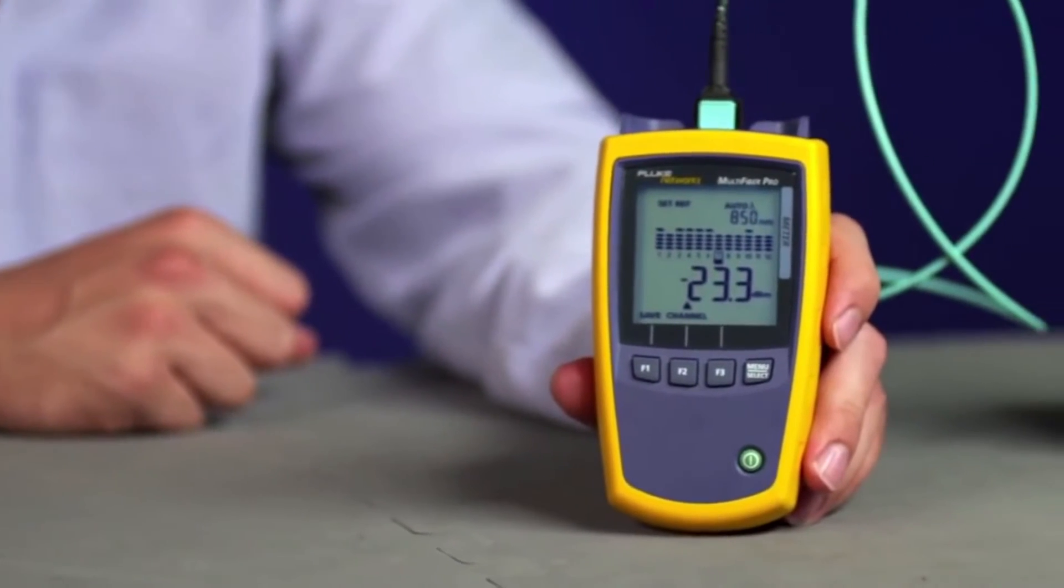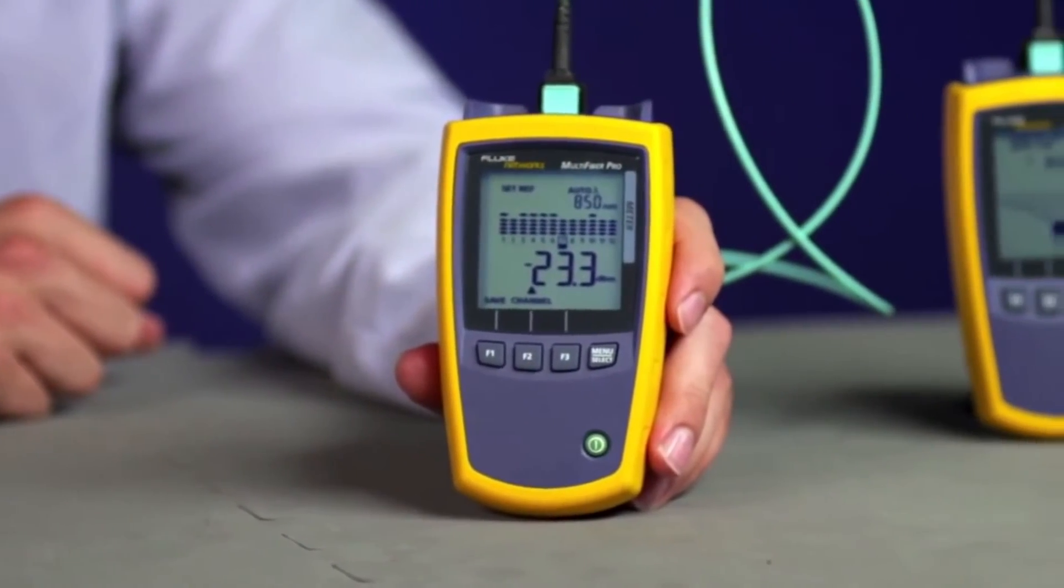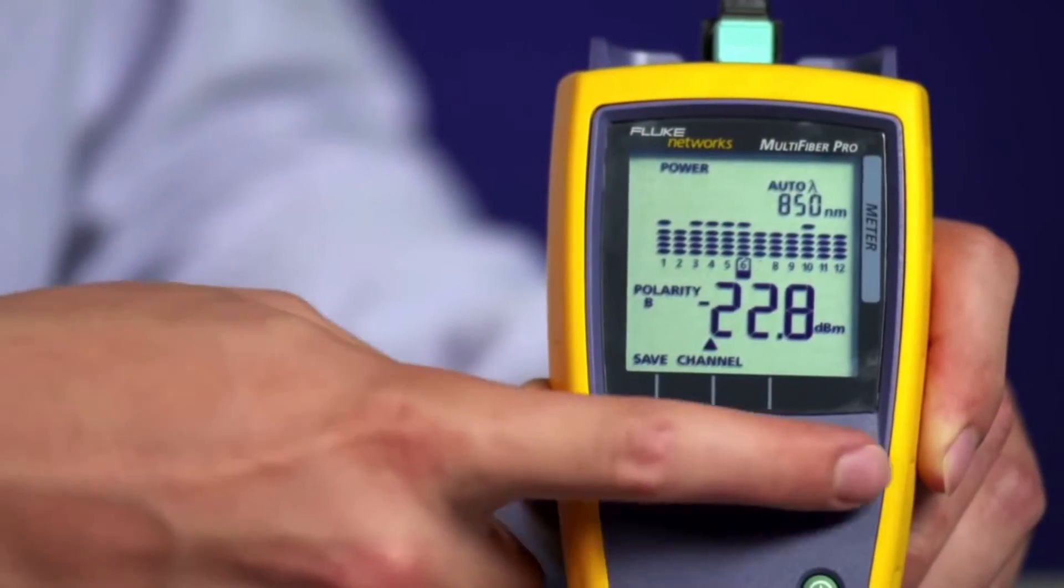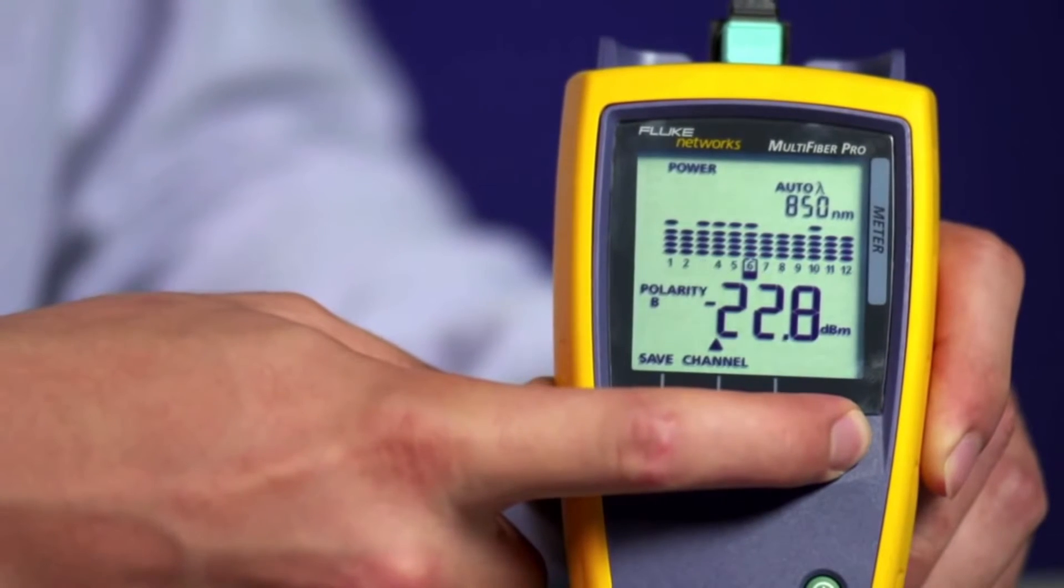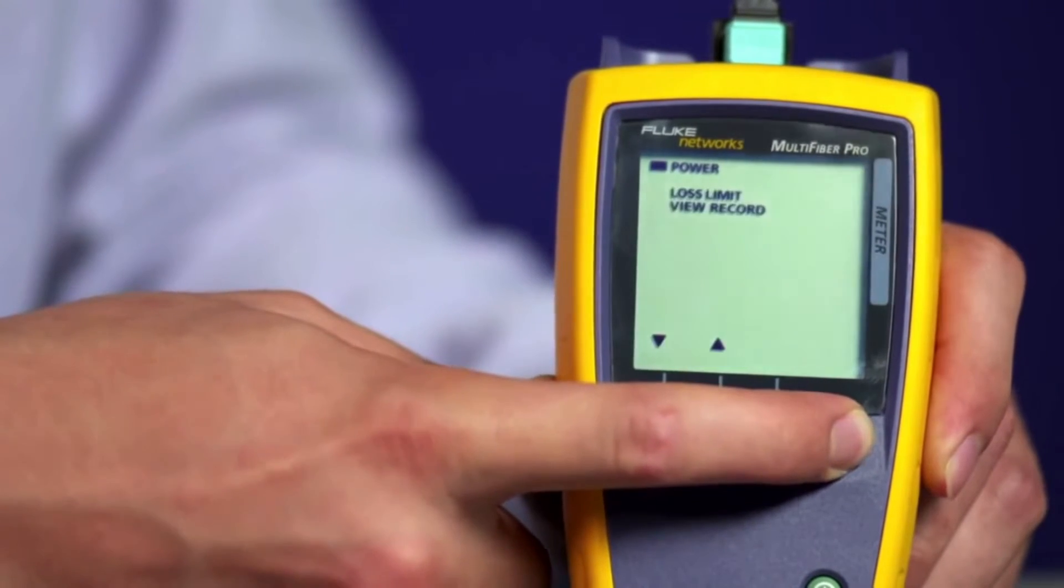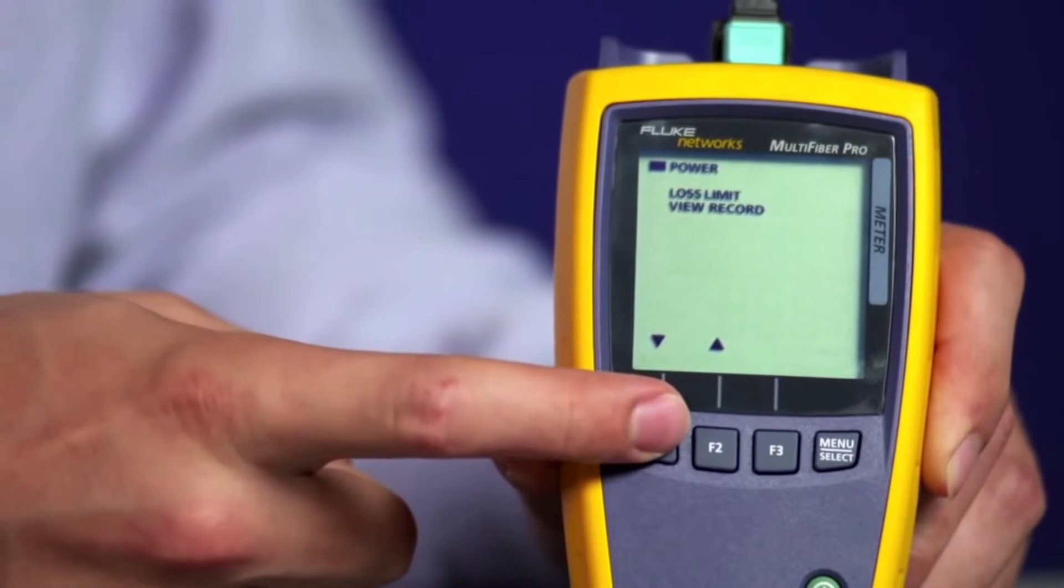After you've set the reference with the supplied MPO test cords, make sure you use the correct loss limit. Press MENU for 3 seconds, then use the arrow keys to move to Loss Limit.